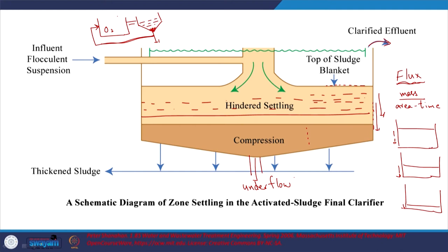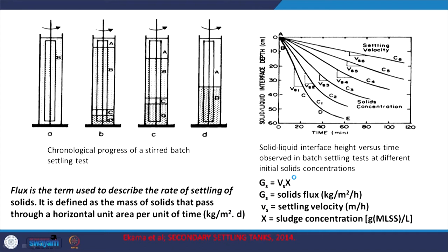There are two fluxes: one due to zone settling and one due to the underflow withdrawal. To obtain these, batch tests are conducted. You can see the settling interface coming down over time for different initial concentrations. The zone settling velocity — the rate at which this interface descends — can be plotted for different concentrations. Solid flux G equals velocity times concentration: velocity has units of L/time and concentration is mass/volume, giving mass per area per time.